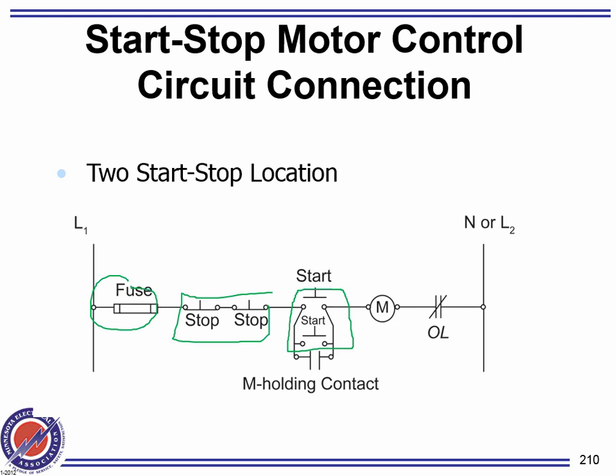The question is, are you required to have a fuse? You can put a fuse anytime. In certain applications, yes, depending on the size of the wire here. Say if that was 12, and depending on the overcurrent protection device ahead of it, you either need a fuse or you don't. Now remember, this is a control circuit, so I can go as low as what? 18 gauge. It's a control circuit.